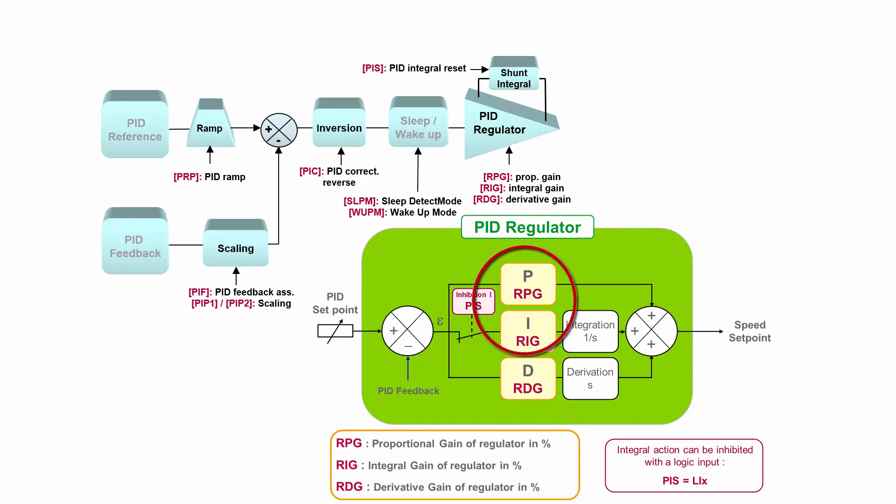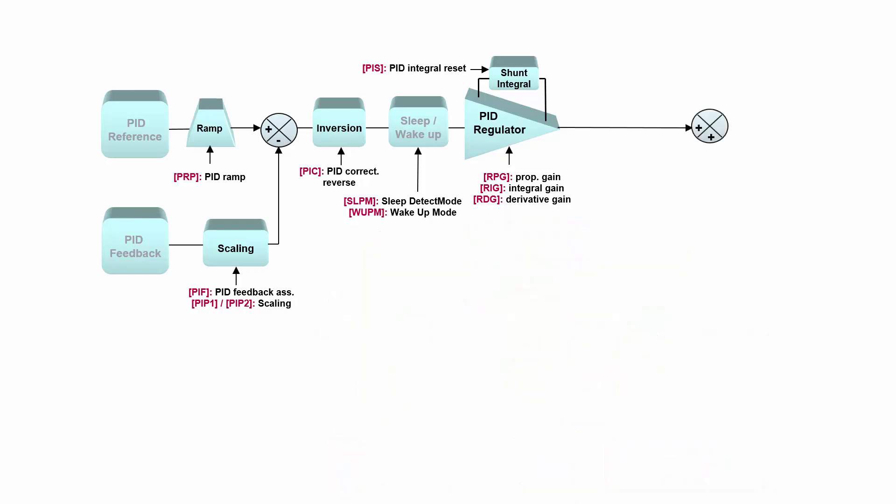Additionally, there is a possibility to inhibit the integrational part. Then output of PID regulator enters an additional summing point, and we will see why. But before entering the summing point, we can set certain limits of our PID output and then additionally ramp up the PID output.